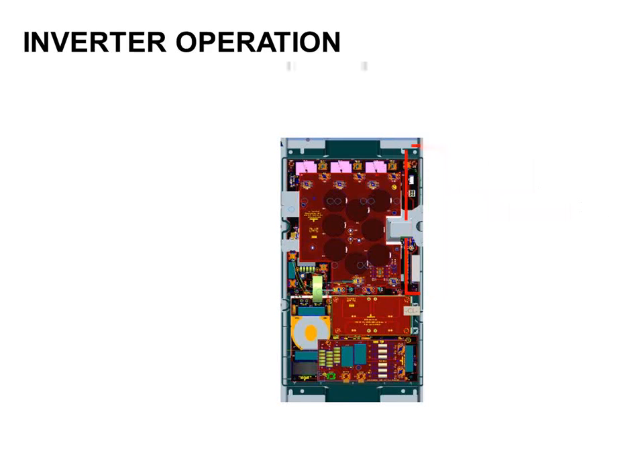The nice thing about having the ability to turn down more on the cooling and heating side is you can also reduce the airflows more. On a normal two-stage heat pump, when I go to single stage, assuming it's 80% on my first stage, I can only turn down my airflow 20%, which makes it harder for me to control that discharge air temperature I was talking about earlier. If I got variable capacity equipment, now I can get some pretty big reductions, and depending on the outdoor temperature and the scenario I'm looking at, I could have as much as a 60% reduction in the airflow. So I can turn down the indoor blower quite a bit, which saves me energy, gives me better dehumidification, and more comfort.